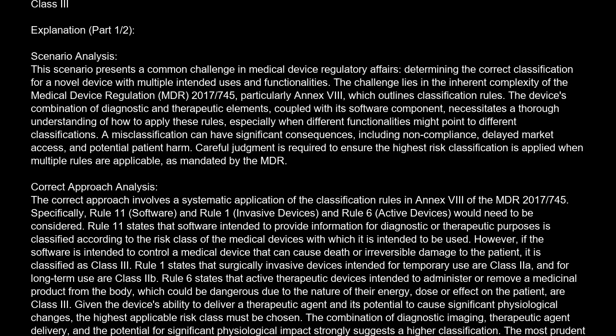Rule 1 states that surgically invasive devices intended for temporary use are Class IIa, and for long-term use are Class IIb. Rule 6 states that active therapeutic devices intended to administer or remove a medicinal product from the body, which could be dangerous due to the nature of their energy, dose, or effect on the patient, are Class III. Given the device's ability to deliver a therapeutic agent and its potential to cause significant physiological changes, the highest applicable risk class must be chosen.